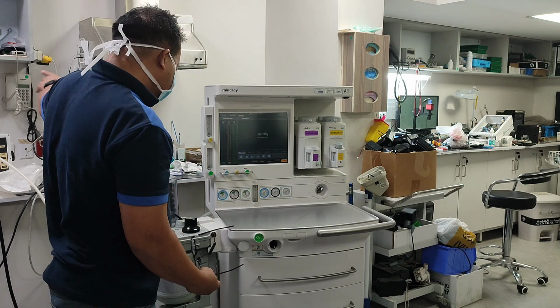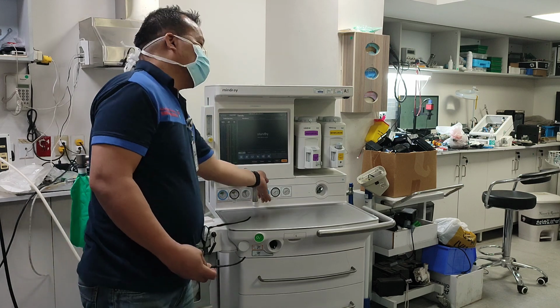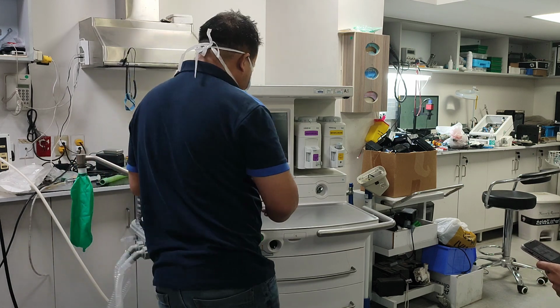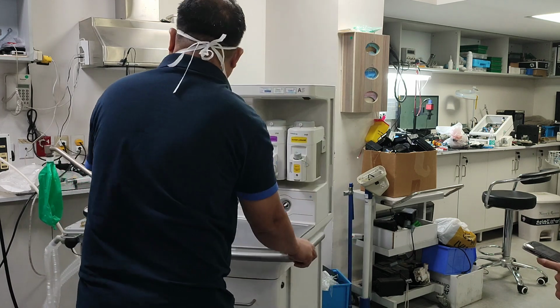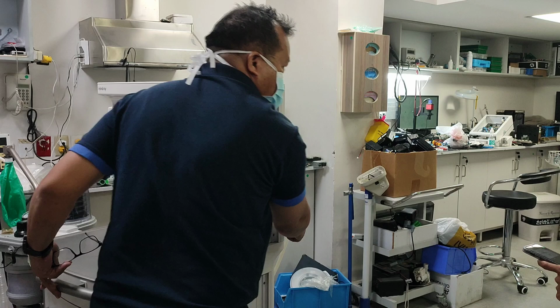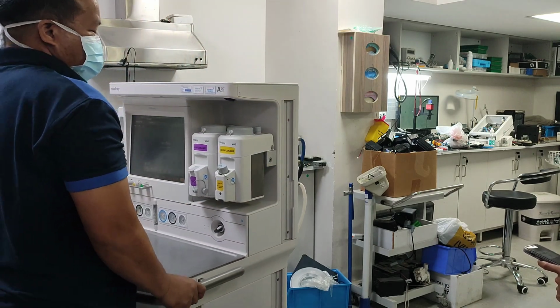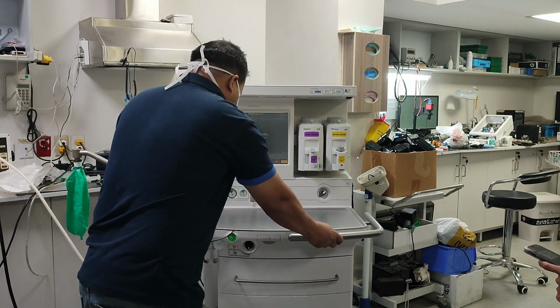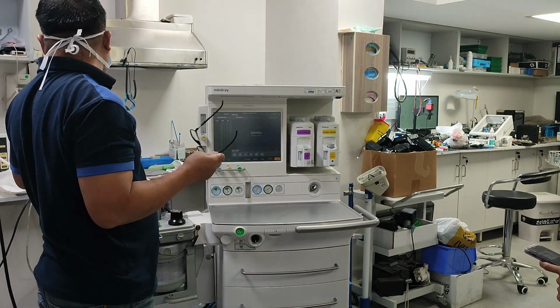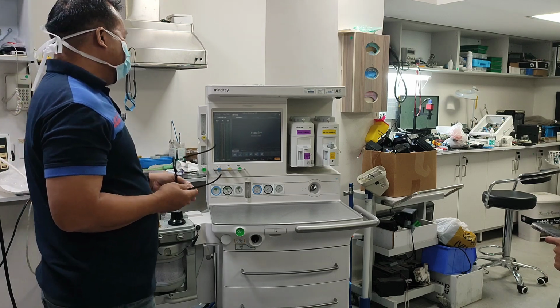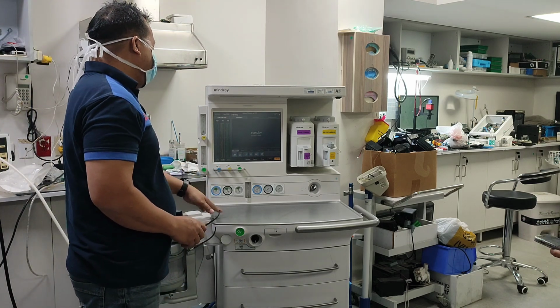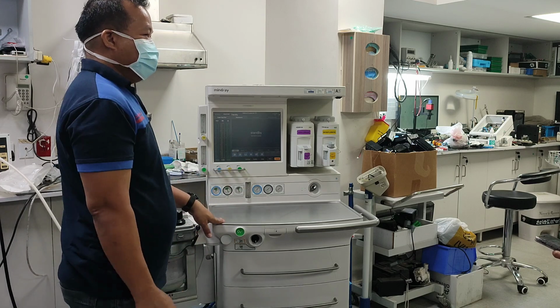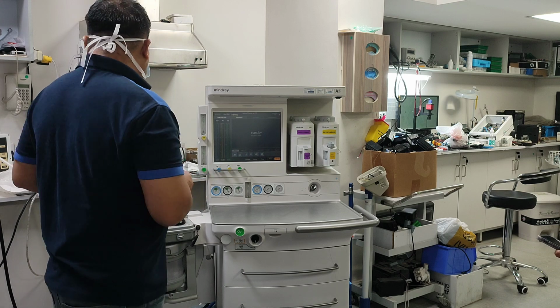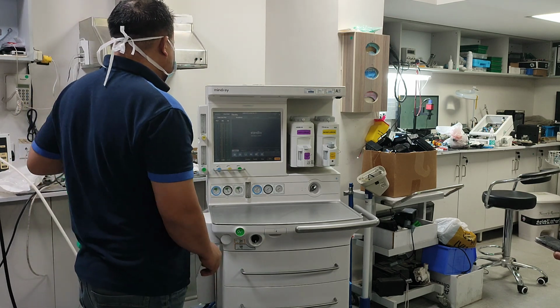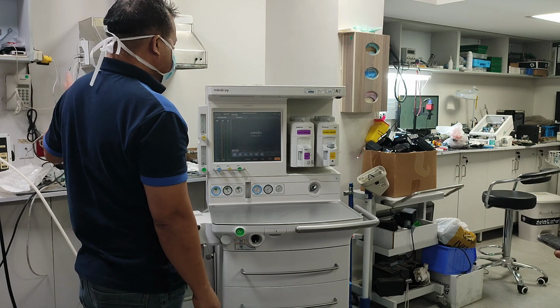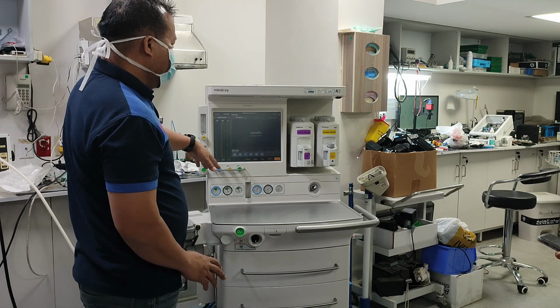This is for the wall mount. This is for the external cylinder. If you see here, there is a backup cylinder at the back. We can put air, oxygen and nitrous there. Sometimes there is a failure of the central oxygen in the wall mount, for example, and there is no oxygen during the operation. So the technicians in the OR will open the cylinder and use it. So there is always a backup in case the wall outlet oxygen fails.